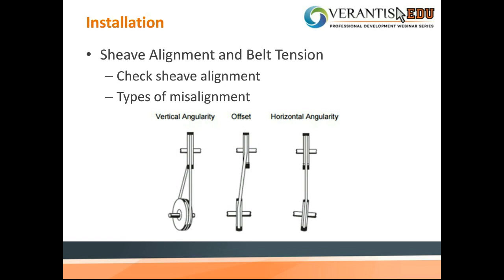There's a couple of different types of misalignment. There's your vertical angularity, which is where the bottom of any of the sheaves is twisted. There's an offset, so instead of being perfectly up and down, we've got something moved over an inch or whatever, maybe moved over a certain amount. And then there's the horizontal angularity, so that's where they're in line, but the angle, the pitch of one of the sheaves, is not perfectly aligned up and down.